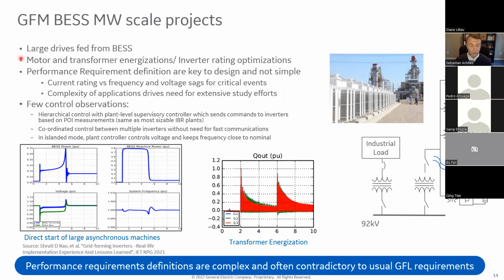So as you know, asynchronous motors have a very large inrush current, so you have to feed like 3 times their rating in reactive current in order to get them to speed up. So doing that from a battery was quite challenging, particularly if you want to keep the rating of the battery limited. So managing the current limitations of the power electronics and at the same time keeping the grid forming characteristics so that the system wouldn't collapse was an important part of these designs.